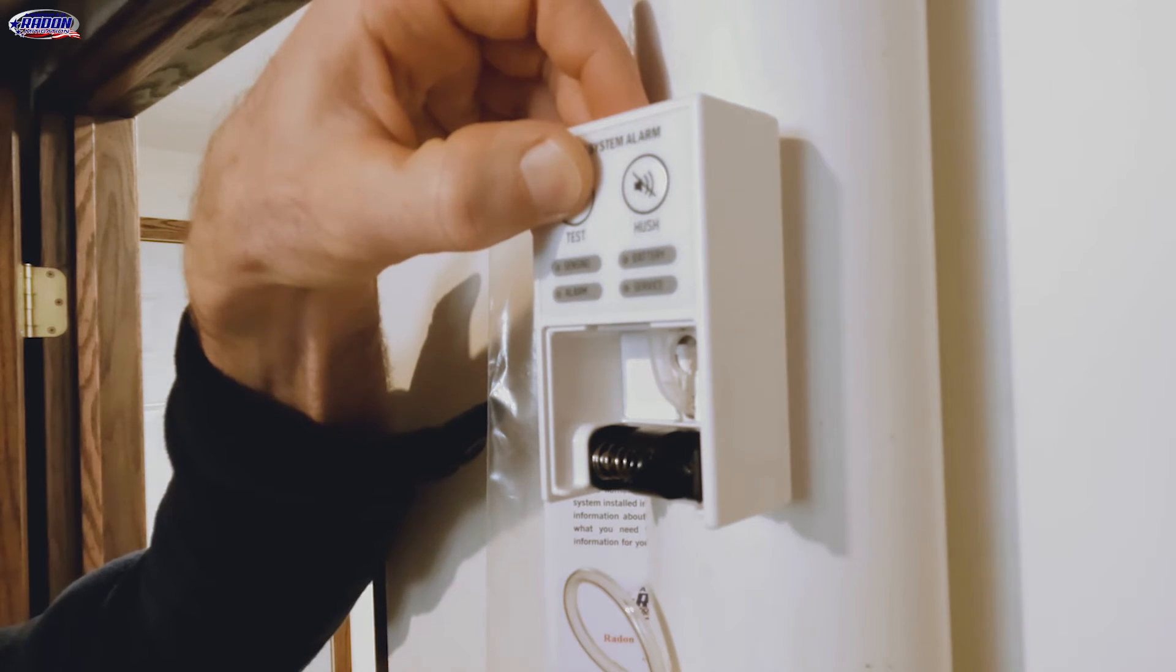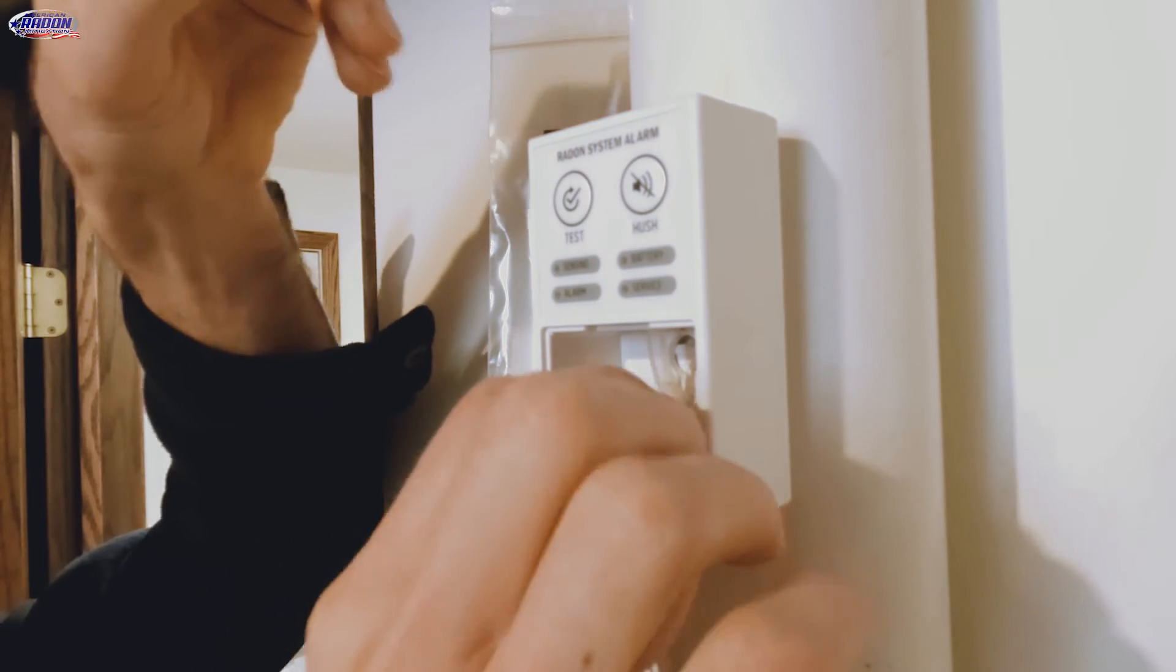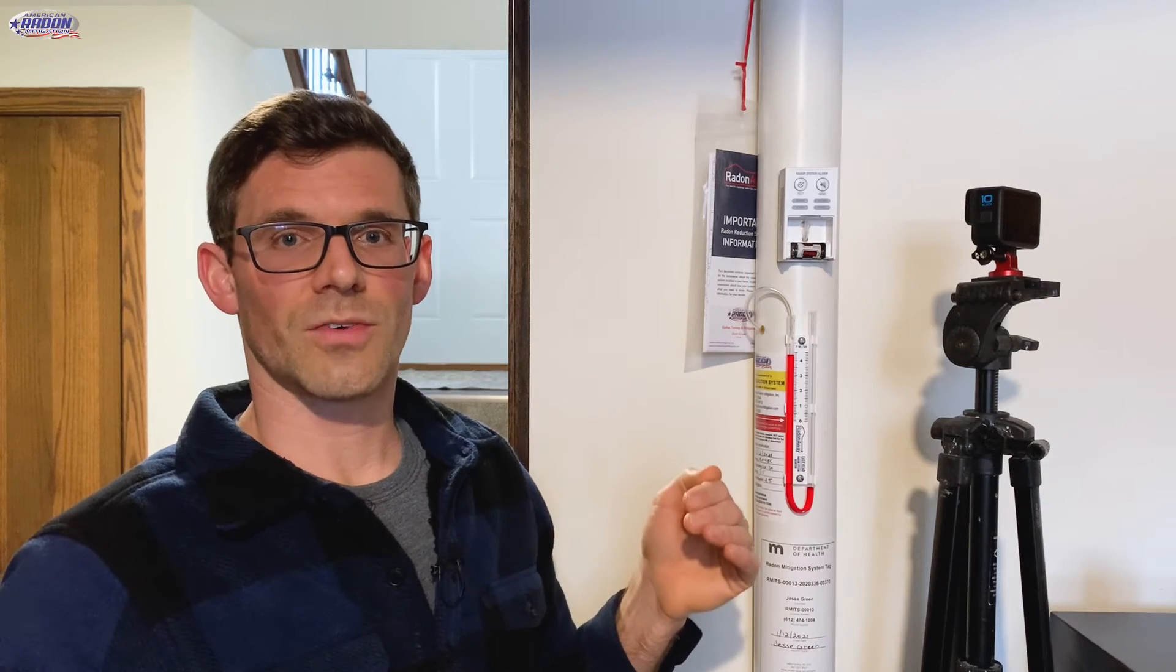So I'm going to push and hold the test button, discharging the power. And then I'll reinstall that battery, and it'll go into its self-calibration mode, which takes about 20 seconds.